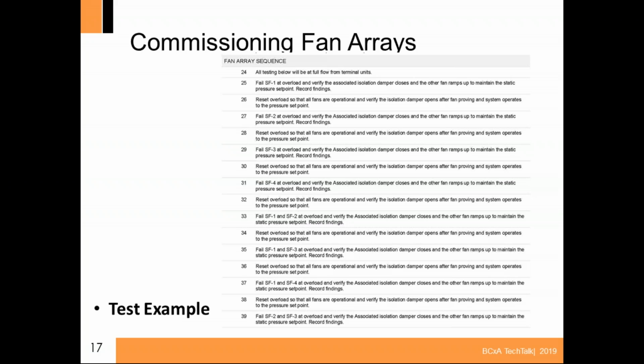So when you do this test script, when you fail the 1 fan and you get your point, what you do is you turn the VFD off, let everything ramp down, reset your motor overload, and then restart the VFD. And you also need to train the staff on exactly how to start and stop these things. It's very important. If not, they're going to just sit and overload the motors, and eventually they're going to turn it all off and then put it in bypass and just run at 60 hertz. If they can, without overloading it.